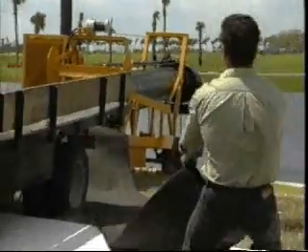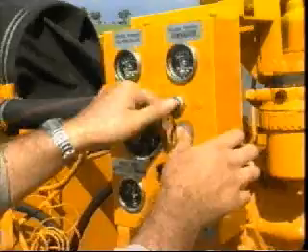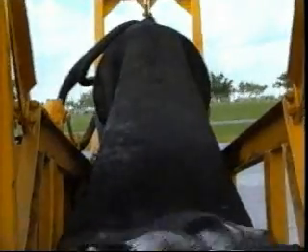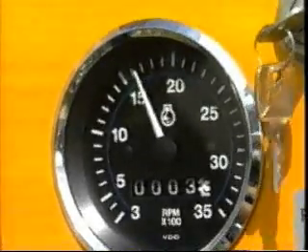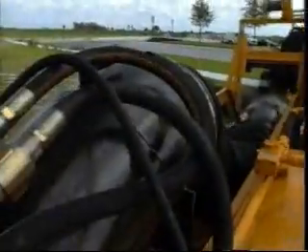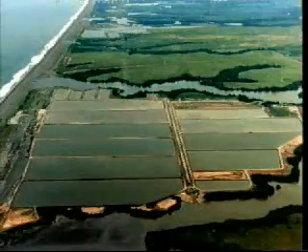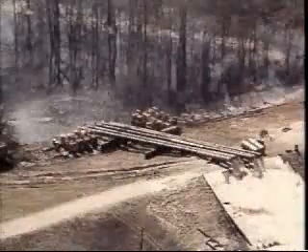Next, unwind the winch and fully extend the discharge hose. The standard mobile is equipped with 50 feet of discharge hose. Additional hose is optional. Start the engine, close the loading valve, and begin pumping. Once the unit is pumping, slowly increase the engine speed. This 24-inch pump can pump up to 17,000 gallons per minute. The Moving Water Industries line of mobile HydroFlows range in capacity from 1,000 gallons to 32,000 gallons per minute. It is especially suited for agricultural, irrigation, and emergency storm drainage.